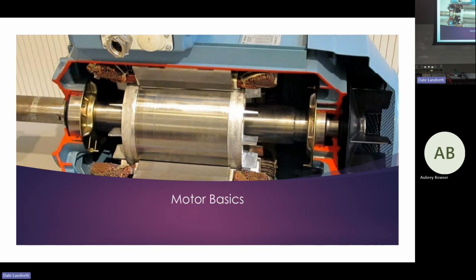So what would cause current in the motor to increase? Voltage drops. What else? I'm not looking, this ain't any trick question. What causes motor current to increase? Failing bearings. Why? Drag. What'd you say? Poor connections. Why? Because it's struggling to make that connection electrically and heating up, which is causing more resistance to the electrical flow. What else? What are some other things? I'm giving you more ideas.